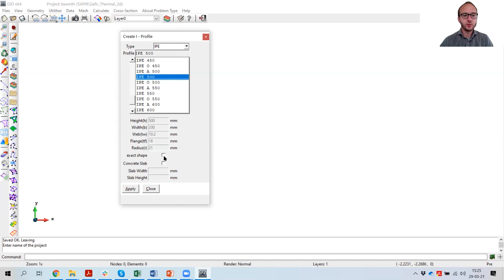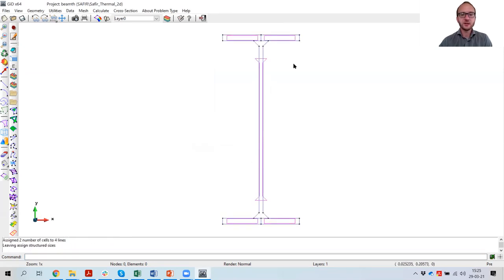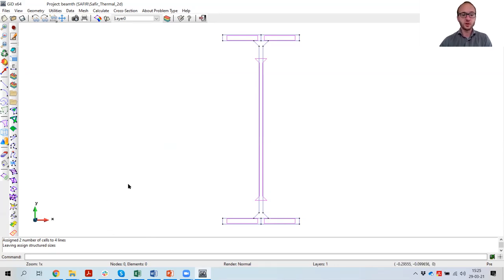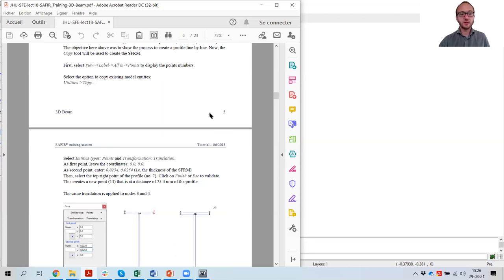We are going to use the pre-embedded dimensions of the IPE 500 profile, so we don't need to select the box for exact shape or for concrete slab. Exact shape would model the root fillet exactly, but here we are going to use rectangles for the flanges and webs — it will help for the definition of the insulation. Let's apply and we get this geometry where the root fillet is slightly simplified as a triangle. Now we have our steel profile, but in this problem it is protected with one inch of sprayed fire resistive material all around the profile, so we have to create this layer of insulation.